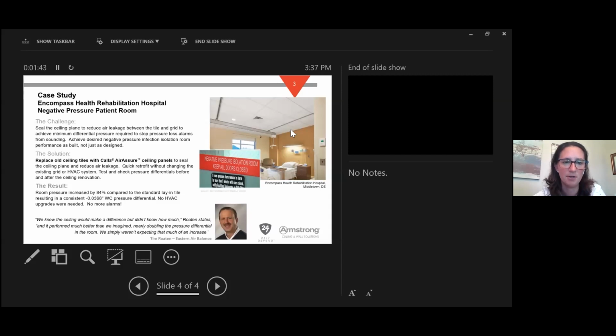The balancer happened to already be in conversations with Armstrong. He said, hey, look, let's try this new ceiling tile from Armstrong. It took about half a day of labor to correct the problem. They had been at negative 0.018 inches of water column. They were trying to get to negative 0.02 inches water column, and they actually got to negative 0.0368.